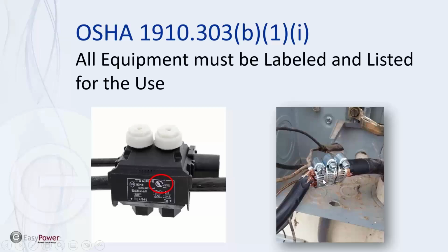It's not anything to do with electrical rating. So the next thing people are going to do is wrap this up with about 15 layers of black tape, which is also not listed to protect against shock from live parts. It's not designed to go onto metal. And if you look at the labeling and listing of black tape, it's a secondary protection, not a primary protection.